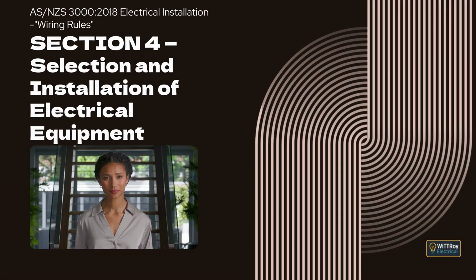Clause 4.5.2.3.1 General requirements. This clause explains that recessed luminaires and their auxiliary equipment must be installed in a way that prevents excessive temperature rise and reduces the risk of fire from ignition of combustible materials. It explains that this can be achieved by using luminaires certified as suitable for contact with combustible materials or insulation, by installing luminaires with tested and classified barriers, or by providing adequate separation from insulation and combustible materials using clearances or fire-resistant barriers.